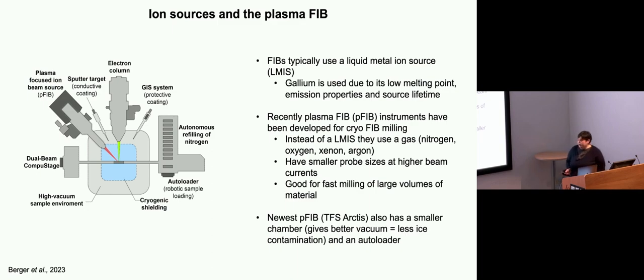Also they've come in slightly rebuilt instruments, so a smaller chamber with more shielding. Some of the advantages can come from not directly from the plasma source but from the chamber. Having, one of the problems with the milling is the buildup of ice contamination. These instruments have massive chambers. So having more shielding or making a chamber smaller may help with that, and also an autoloader just to make workflows a bit easier.